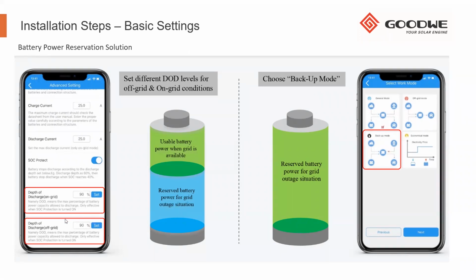The off-grid is normally recommended to just use the maximum amount for the battery type that you are using. In this case, I think this was a big BYD pack, so we could set it to 90%. And then the depth of discharge on grid, we can set to 50% or 40% to make sure that we reserve some battery for outages. Backup mode will only listen to the off-grid depth of discharge. It will ignore the on-grid depth of discharge.